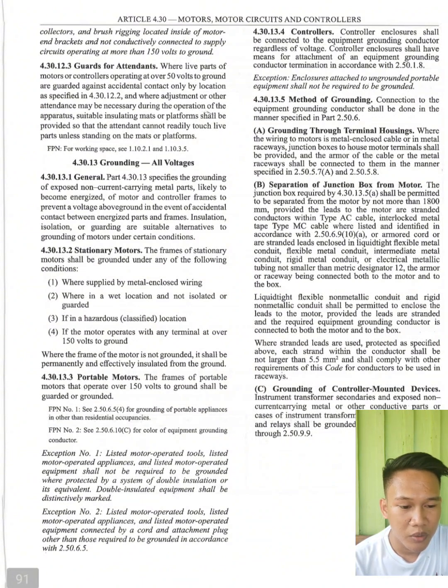Liquidtight flexible nonmetallic conduit and rigid nonmetallic conduit shall be permitted to enclose the leads to the motor, provided the leads are stranded and the required equipment grounding conductor is connected to both the motor and the box. Where stranded leads are used as specified above, each strand within the conductor shall be not larger than 5.5 mm squared and shall comply with other requirements of this Code for conductors to be used in raceways. C. Grounding of controller-mounted devices. Instrument transformer secondaries and exposed non-current-carrying metal or other conductive parts or cases of instrument transformers, meters, instruments, and relays shall be grounded as specified in 2.50.9.1 through 2.50.9.9.